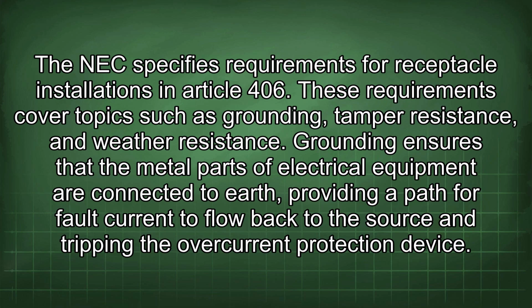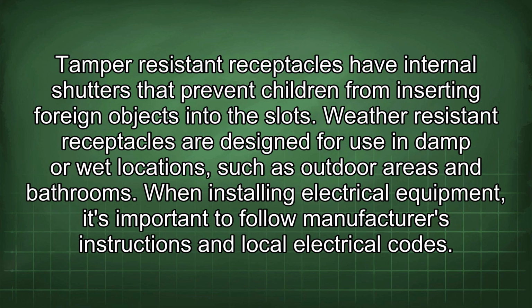Grounding ensures that the metal parts of electrical equipment are connected to earth, providing a path for fault current to flow back to the source and tripping the overcurrent protection device. Tamper-resistant receptacles have internal shutters that prevent children from inserting foreign objects into the slots. Weather-resistant receptacles are designed for use in damp or wet locations, such as outdoor areas and bathrooms.